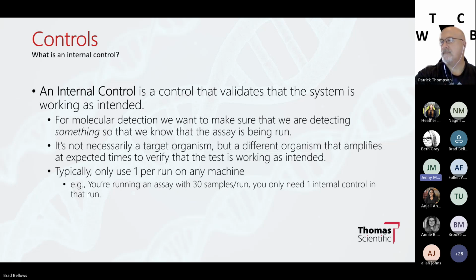Typically, depending again on the level of your certification and that of your technicians, you can run one internal control per run on any specific machine. So for example, you're running an assay with 30 samples for one run in a single machine. You would only typically need one internal control in that run. So this one isn't necessarily the most cost prohibitive, but it does add up if you're running multiples of 30 samples. If you're running like 10 times 96 well plates, it can get very expensive.